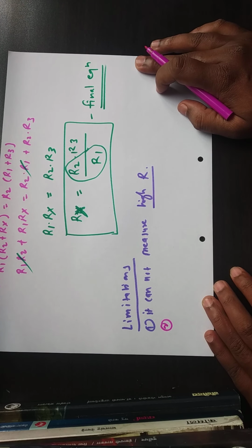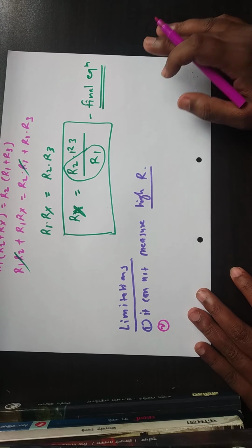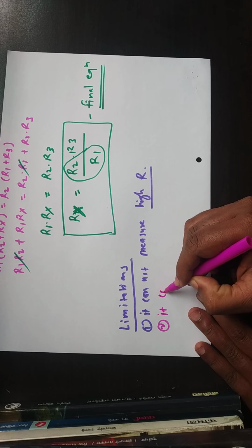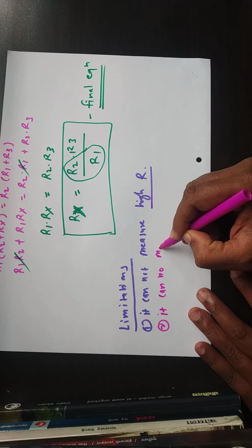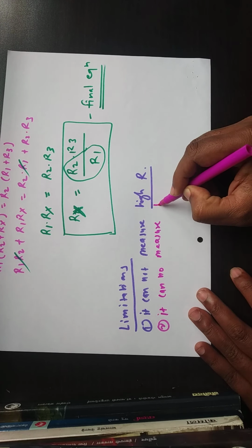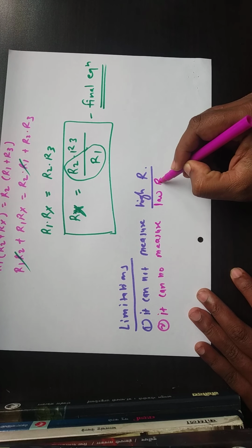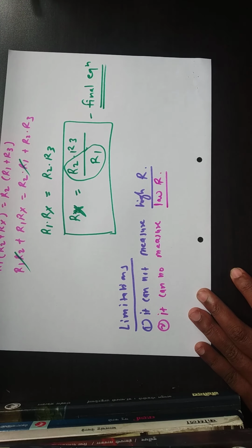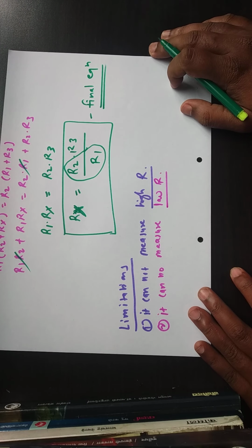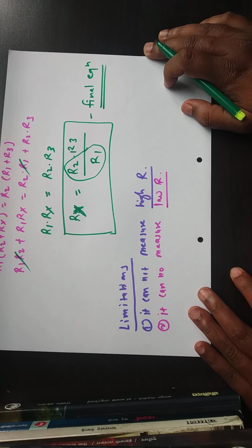It cannot measure the low resistance. In the case of low resistance measurement, your lead and contact resistance become significant.